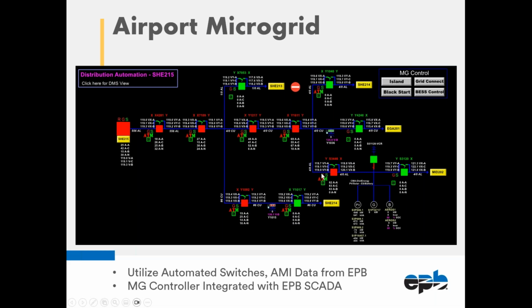As you can see on this feeder, there are actually a lot of ties to other circuits. This is kind of in the middle of town, so it has a lot of redundant options from other feeders. However, if there was a case where none of these options were available, what we can do now is open this switch so that we're completely isolated from the traditional grid.